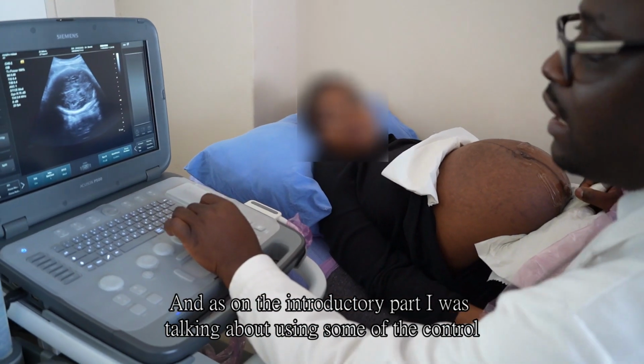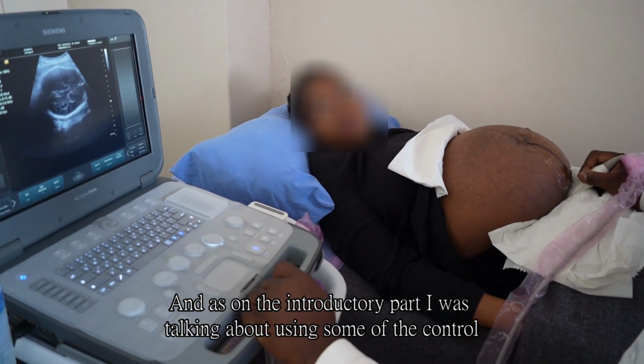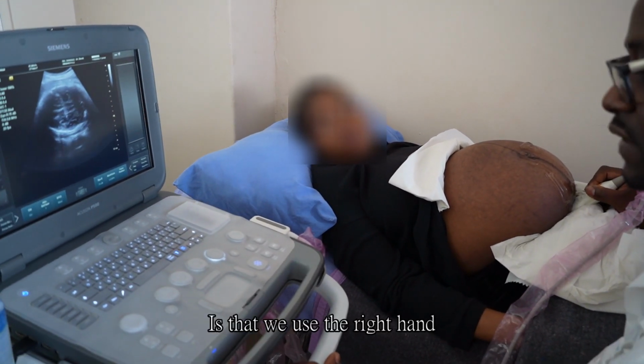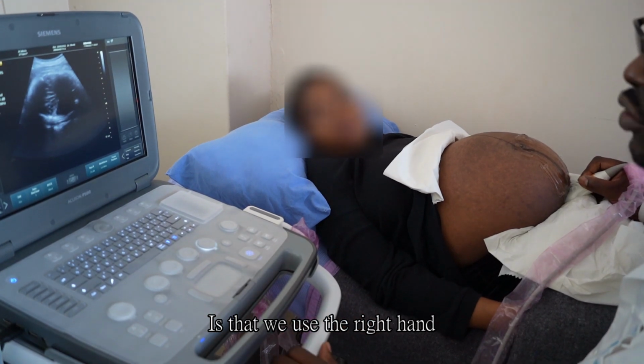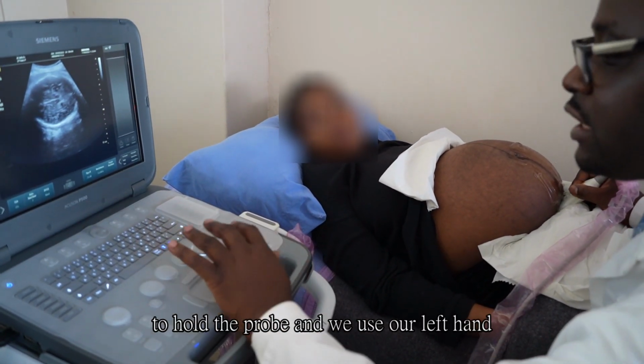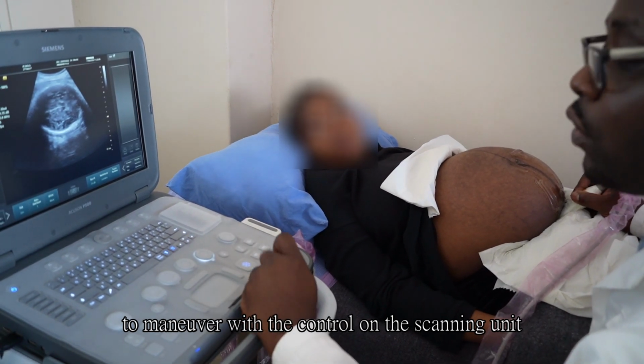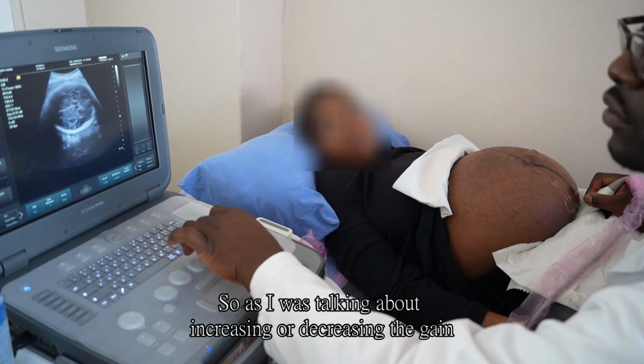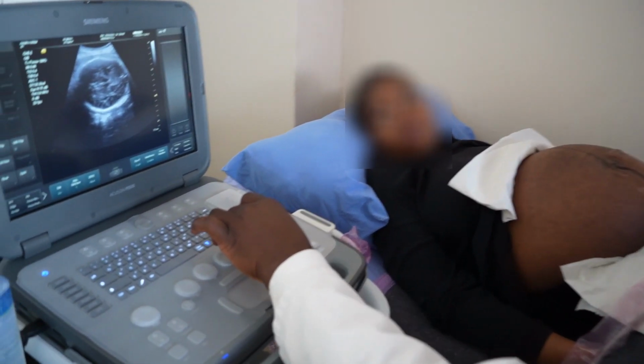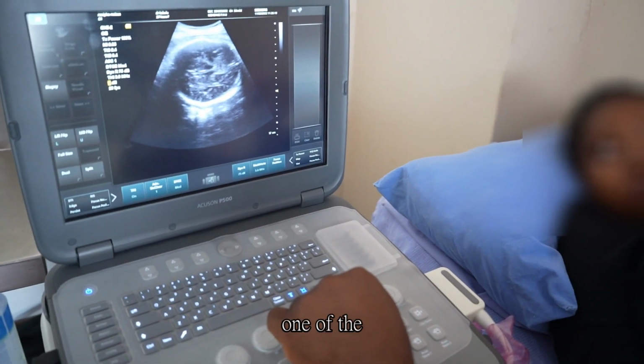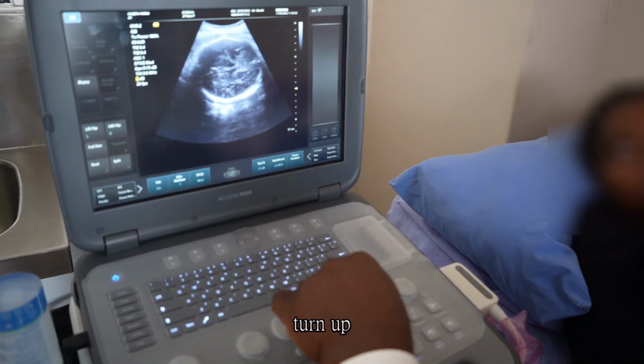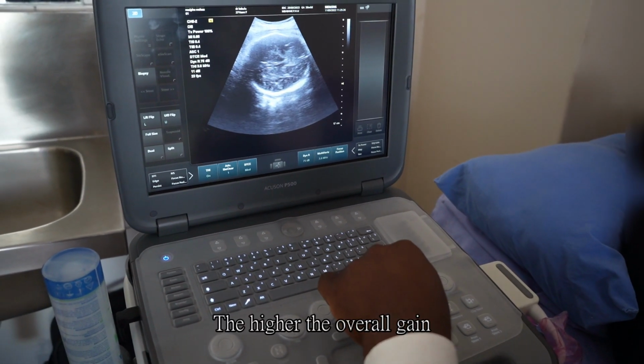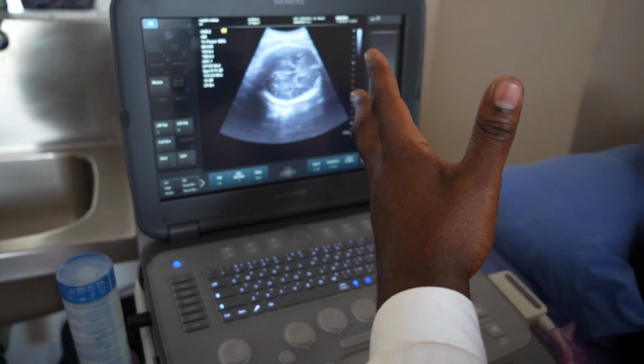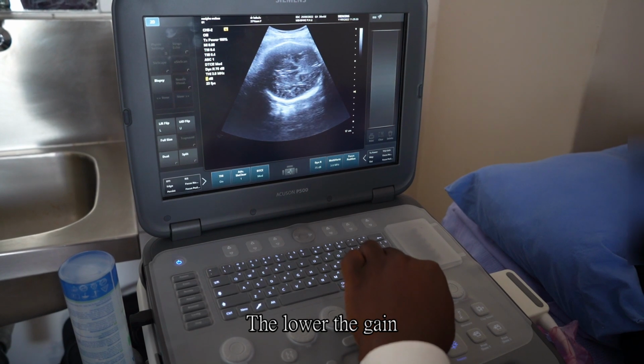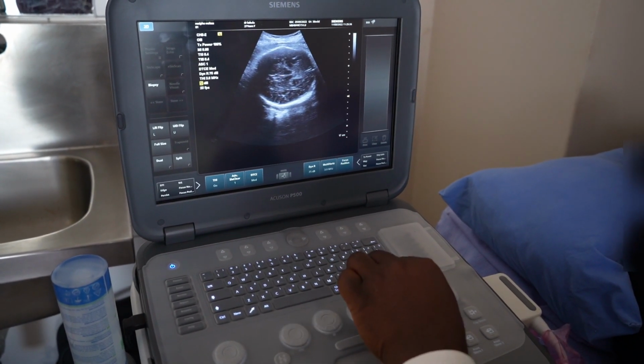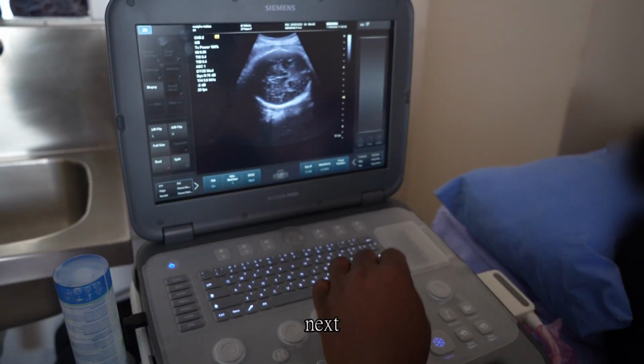As in the introductory part, I was talking about using some of the controls. We use the right hand to hold the probe, and we use our left hand to maneuver the controls on the scanning unit. As I was saying about increasing or decreasing the gain, it is just turning as one would turn up the volume on the stereo. The higher the overall gain, the brighter the image. The lower the gain, the darker the image, as we can see using this scale.